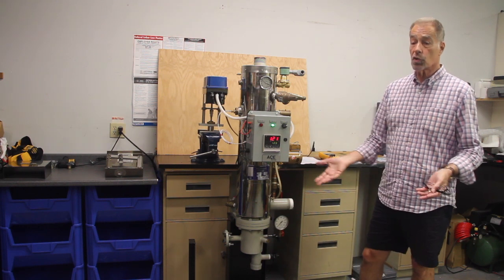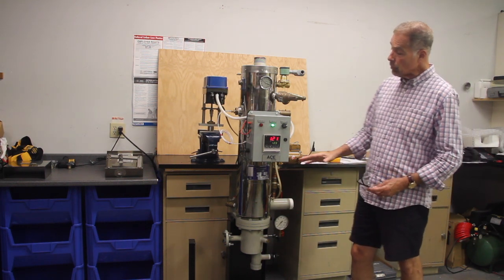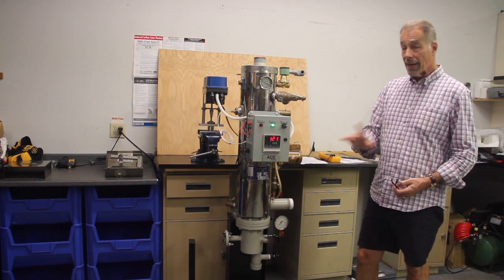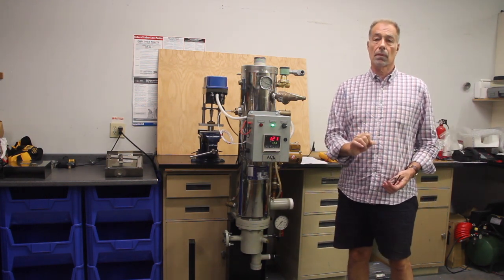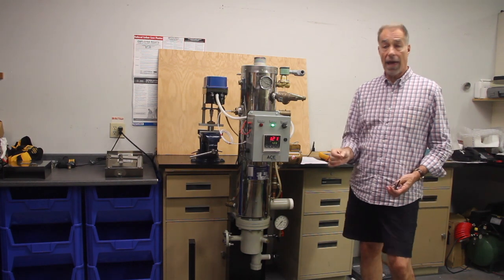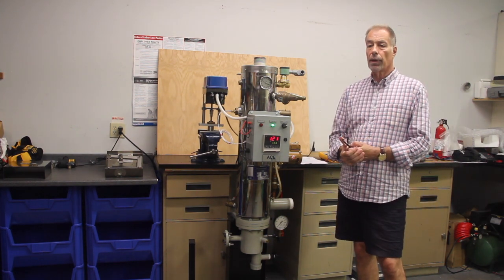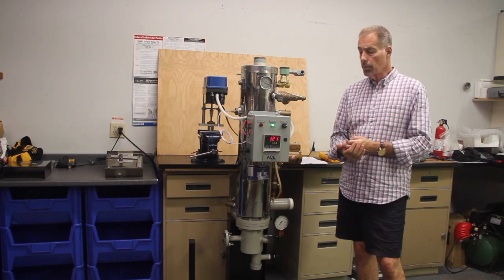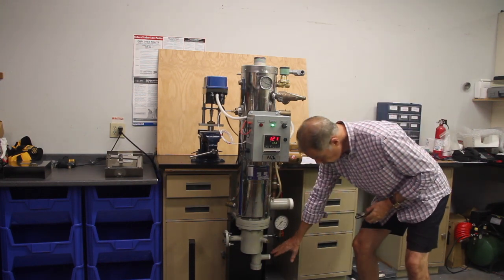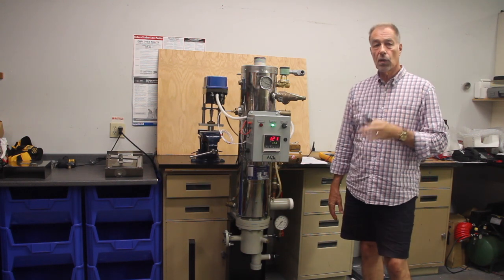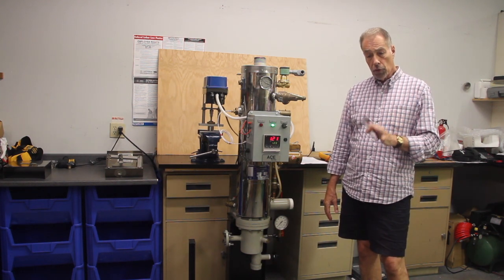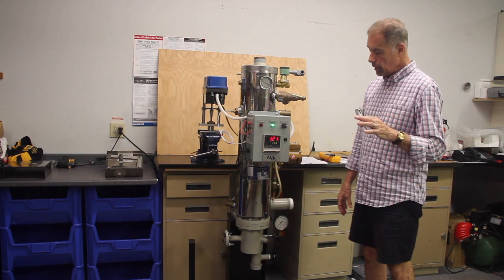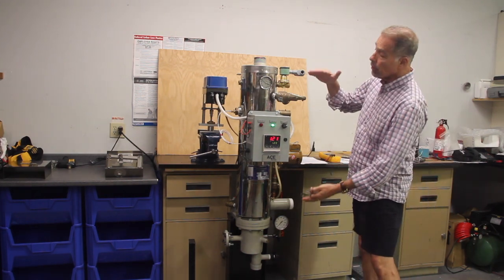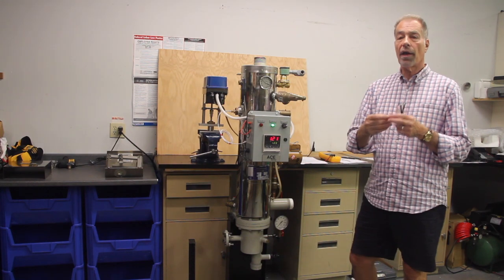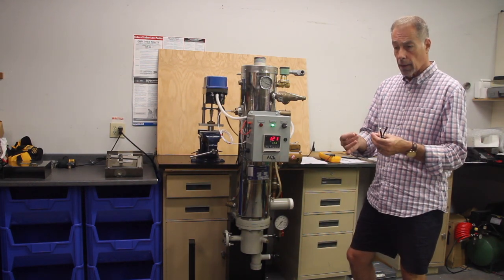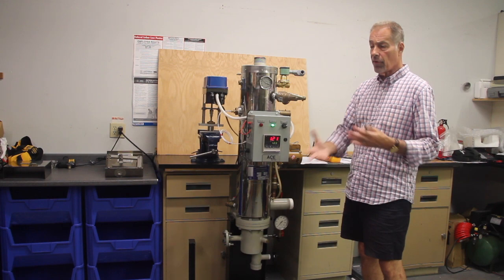when it's discharged to atmosphere. So we're now delivering condensate temperatures by design of 160. And very often we go much below that. But from a spec standpoint, we can guarantee that the condensate will be delivered out of this orifice here at 160 or below. That's the good news. It's highly efficient. It's very unique. It does require more surface area. It does require heavier wall tubing because when steam hits condensate, it's a little bit violent.